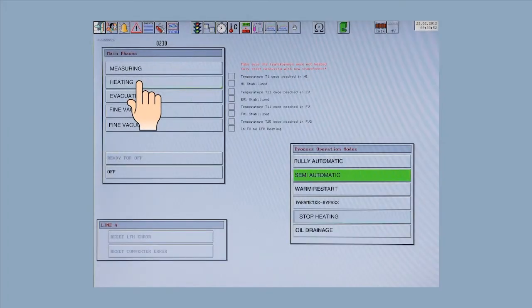The maximum and minimum currents needed for the process are determined. The maximum power needed for the process is determined. The currents below the maximum for the average and high voltages are set. If all the measurements are correct and meet specification, then the Heating 1 sequence will be allowed. Heating 1 step.